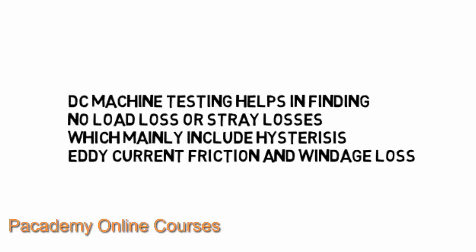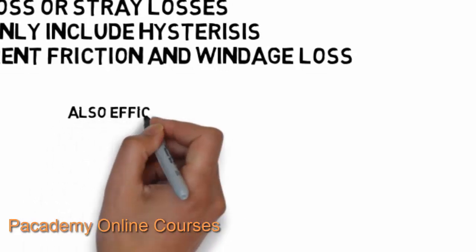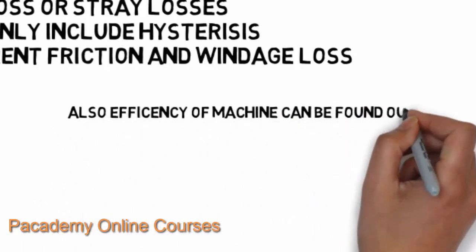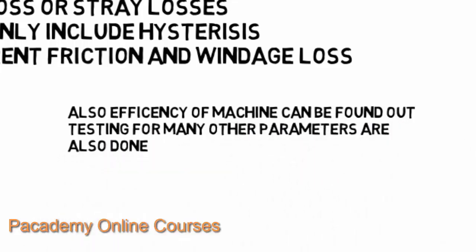These kinds of tests are applicable to both DC motors and DC generators. We will talk about the Swinburne's test, which is mainly used to test shunt motors and cumulatively compounded wound motors that have a constant flux, or where flux does not vary much with armature current. These tests also help in finding the efficiency of the machine.